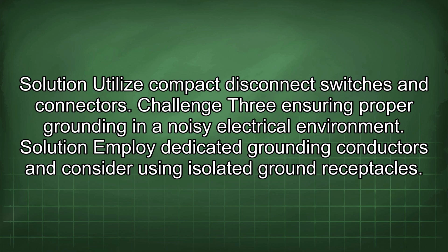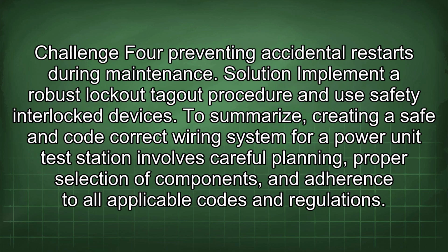Challenge 3: ensuring proper grounding in a noisy electrical environment. Solution: employ dedicated grounding conductors and consider using isolated ground receptacles. Challenge 4: preventing accidental restarts during maintenance. Solution: implement a robust lockout-tagout procedure and use safety interlocked devices.